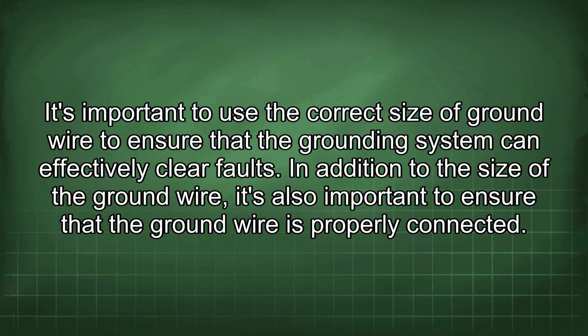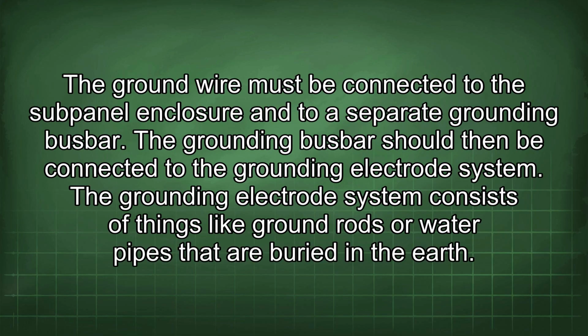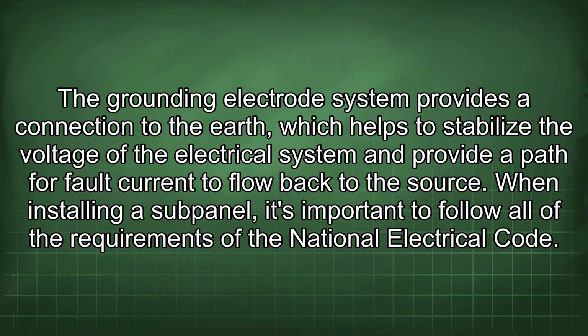In addition to the size of the ground wire, it's also important to ensure that the ground wire is properly connected. The ground wire must be connected to the subpanel enclosure and to a separate grounding bus bar. The grounding bus bar should then be connected to the grounding electrode system. The grounding electrode system consists of things like ground rods or water pipes that are buried in the earth. The grounding electrode system provides a connection to the earth, which helps to stabilize the voltage of the electrical system and provide a path for fault current to flow back to the source.